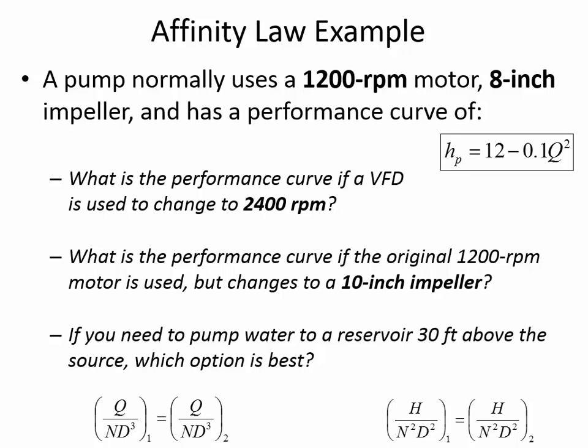So if someone asked, what's better? Is it better to keep the 8-inch and spin it twice as fast? Or is it better to increase the impeller diameter from 8 inches to 10 inches? You can look at this new pump curve and see that spinning it faster gives you a greater increase in the lifting capacity of the pump. If you have a bigger diameter, rather than spinning it faster, you're not going to increase the lifting capacity nearly as much. Okay, we're out of time. If you need a pump to lift it 30 feet, the one that's best is this one. This one wouldn't pump the water 30 feet because it can only pump the water at most 18.75.